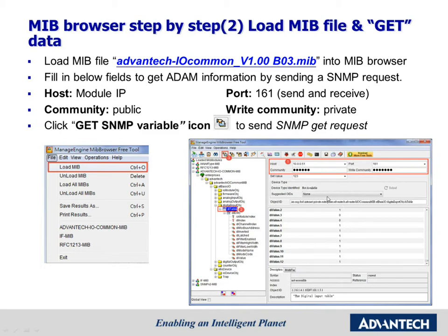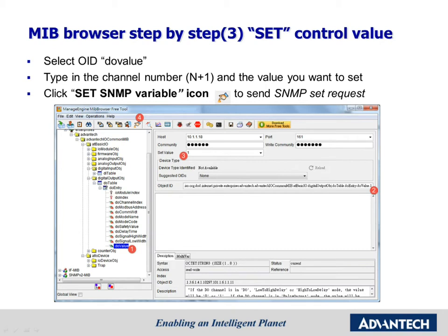Here we get the DI values. This is an example of setting a DO channel. First, we have to select the DO values in the hierarchical tree. As we can see, the OID of the DO value is shown here. For channel 0 of ADAM 6266, its OID would need to add .1 at the end. So we have to type .1 at the end of the OID. For high logic, we type 1; for low logic, we type 0 in the set value. Then send out the SNMP set request by pressing the SET button.